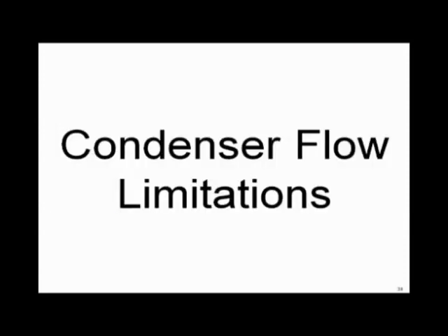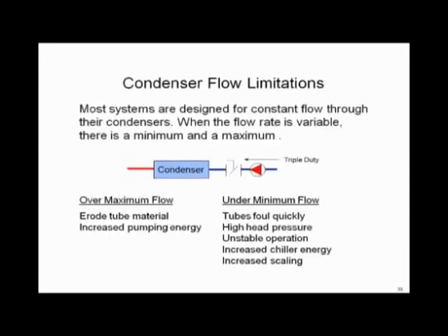How about condenser water flow limits? Is there a maximum flow for the condensers themselves? Yes. If you overflow the condensers, you'll erode the tubes. Most centrifugal or reciprocating condensers have a maximum velocity of 8 to 8.5 to 9 feet per second. Exceeding those numbers keeps tubes clean but causes erosion, making the tubes very thin — a serious problem. And beyond that, why waste all that pumping energy pushing flow through something that doesn't need it?